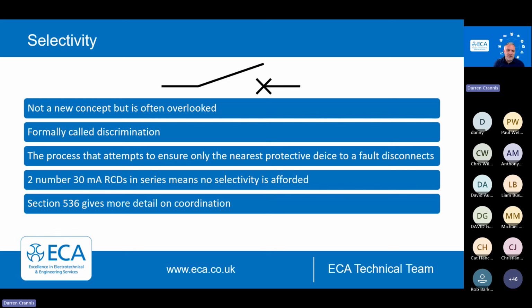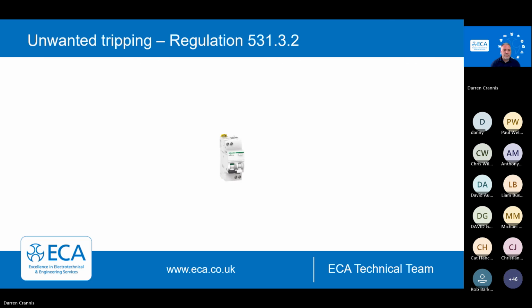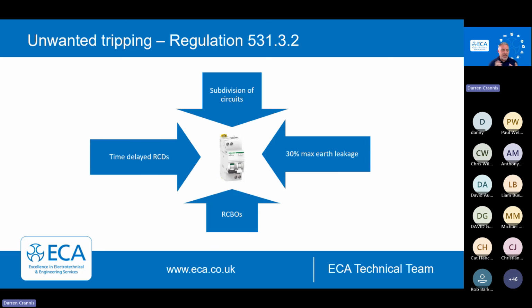You'll get partial selectivity there. If there is a fault, one or other will disconnect. I wouldn't worry about that too much. That's generally quite hard to achieve in that situation. It's fearful of unwanted tripping. I'd like to think things are getting better on that, but there are things we can do with this. And I think we've been doing that naturally over the years anyway. We've been looking at things like splitting the circuits up. And that does really help as well, about that whole 30 milliamp earth leakage, trying to minimize the effects of excessive earth leakage onto our RCDs.